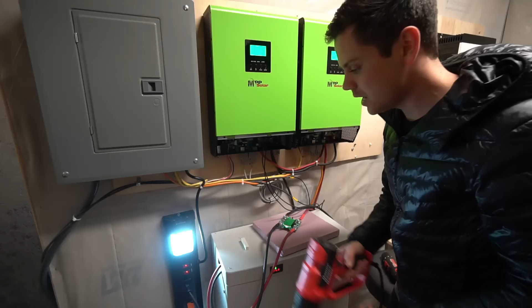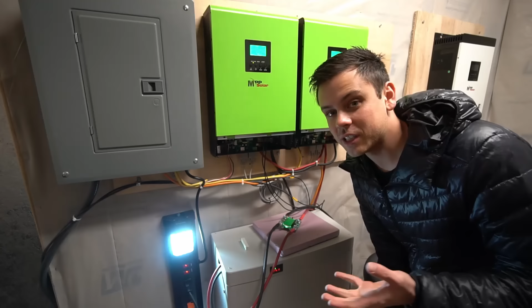Now we're going to add a heat gun. The circuit breaker on here can handle 63 amps, so let's crank this to 40 amps. And if this is a 5 kilowatt hour pack, a 1000 watt load is perfect, and we're pushing 850 to 1000 watts. So this is perfect load for this test.